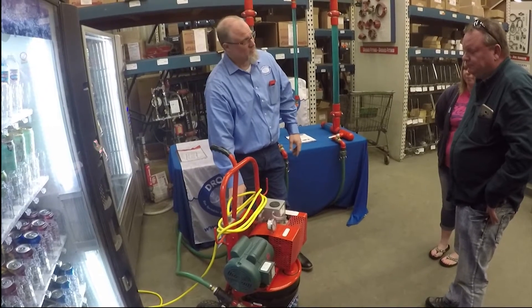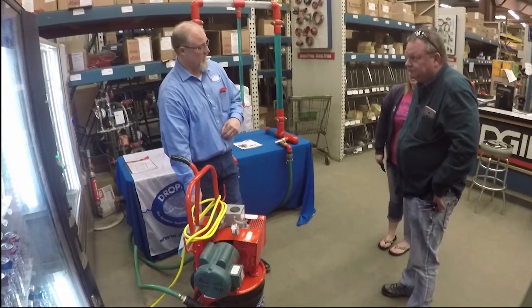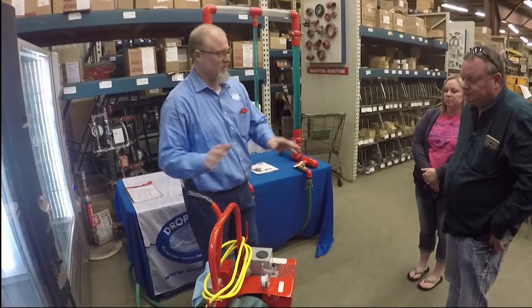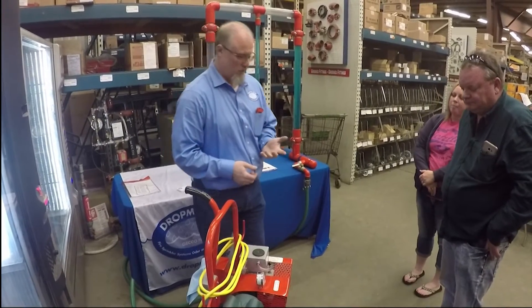You need to drain this down daily. The one thing I can guarantee you about this machine is if you do not drain the oil out of this muffler every day and it fills up with oil, from that muffler 16 feet back and about 12 foot square, you are going to cover everything in oil. So every day, drain the oil out and you won't have any problems.